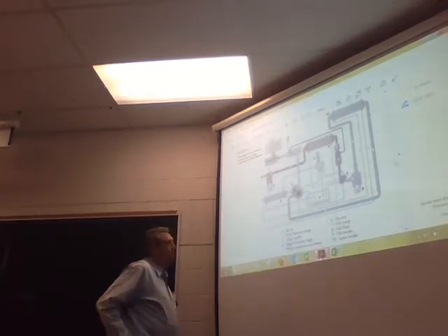Then from the aftercooler, you're going to go to another water separator and air out. See that? And then the other side of that is going to be the loop system. So you can see that the other smaller line that you see there is the lubrication side. So you're going to see the oil sump, the oil filter, the oil cooler, and the oil intercooler. So if you follow the little arrows on the oil system, this would be oil sump in here. So you can see where the oil then comes from here, goes through, follow the little arrows, and goes back to the other stage, back up through, cooled again, back into the sump.